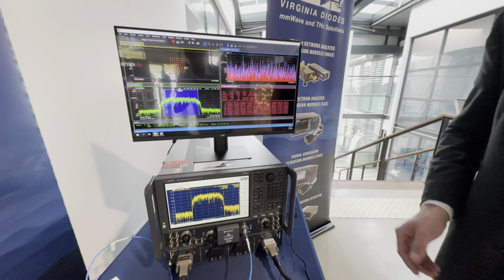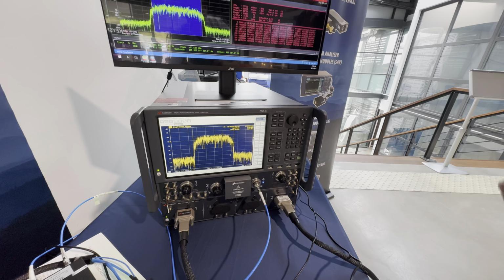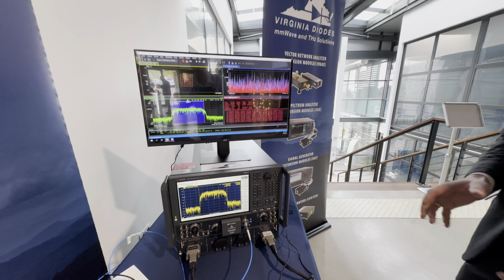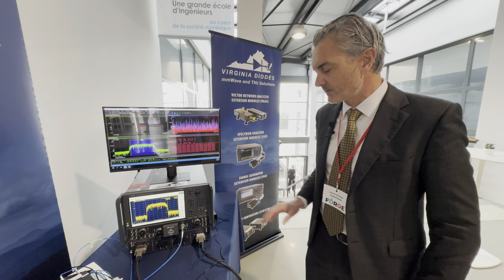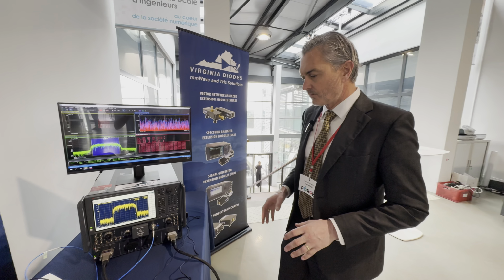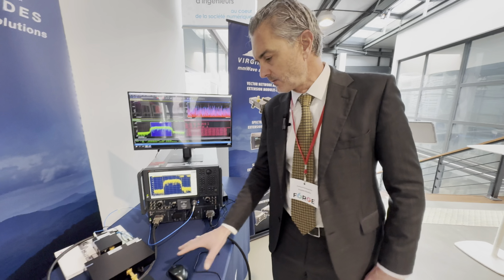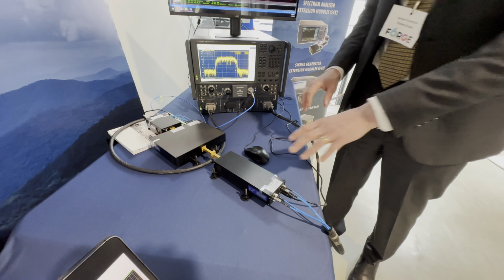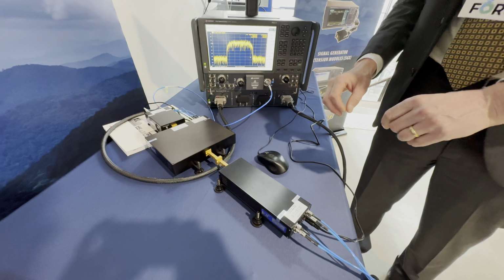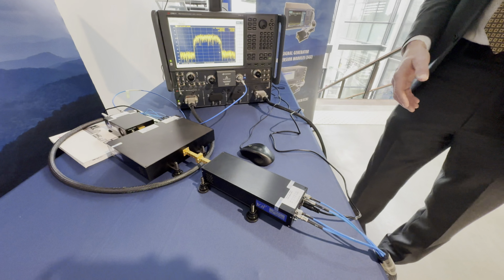Out of the box, the Keysight PNA works from DC to 67 gigahertz, and on its own, it's capable of doing vector component analysis in those frequencies. Traditionally, our support for a PNA would be two heads like this, one on either side, so that you could do S-parameter measurements of the device under test.